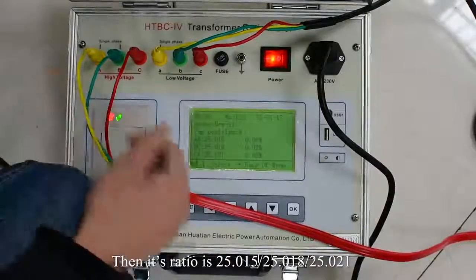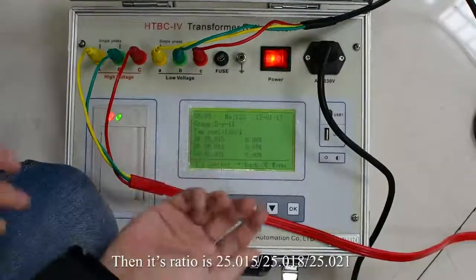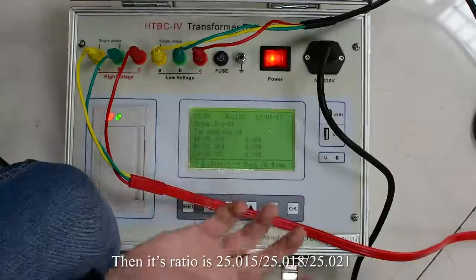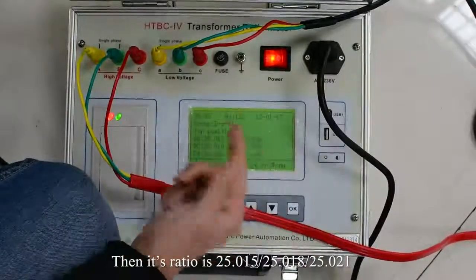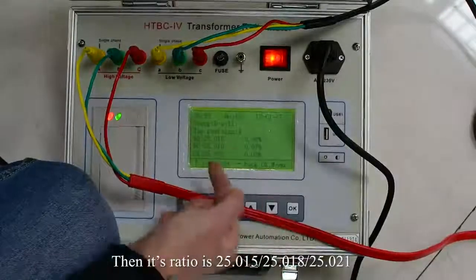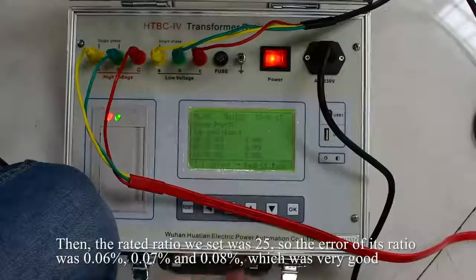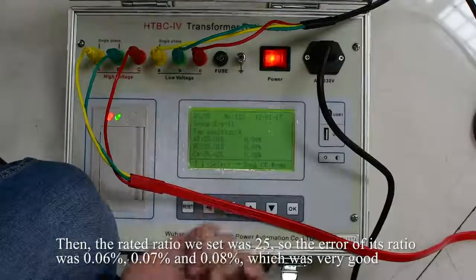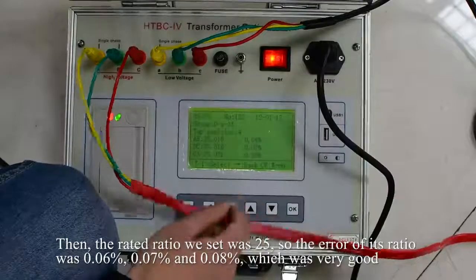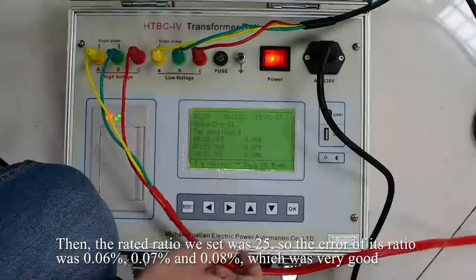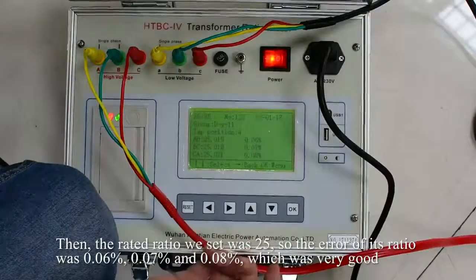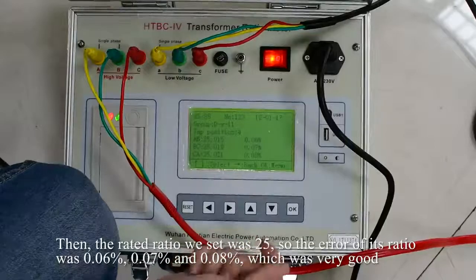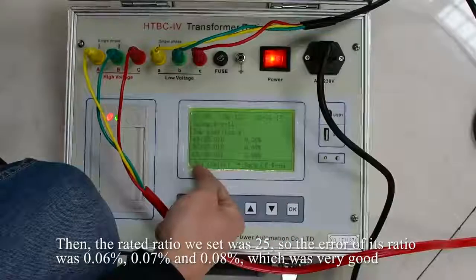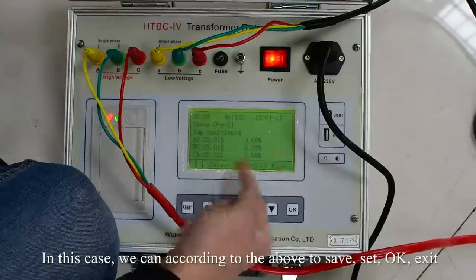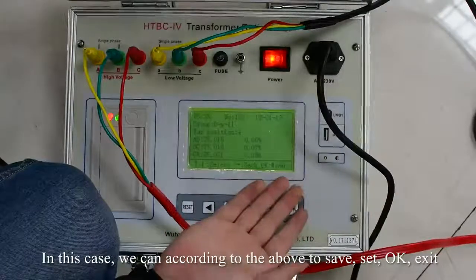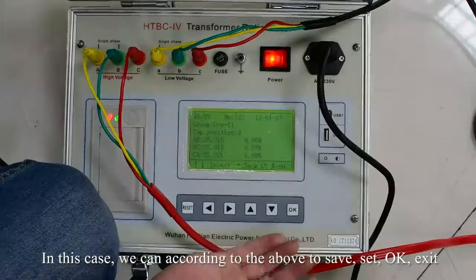Then its ratio is 25.015, 25.018, and 25.021. Then the rated ratio we set was 25, so the error of its ratio was 0.06%, 0.07%, and 0.08%, which was very good. In this case, we can, according to the above, save, set, OK, exit.